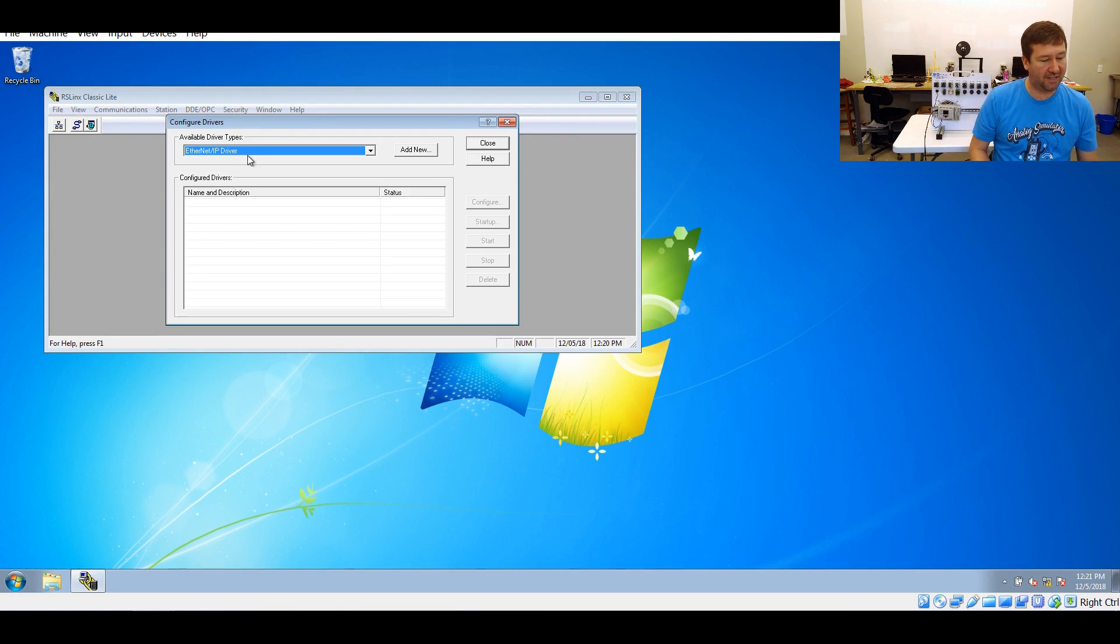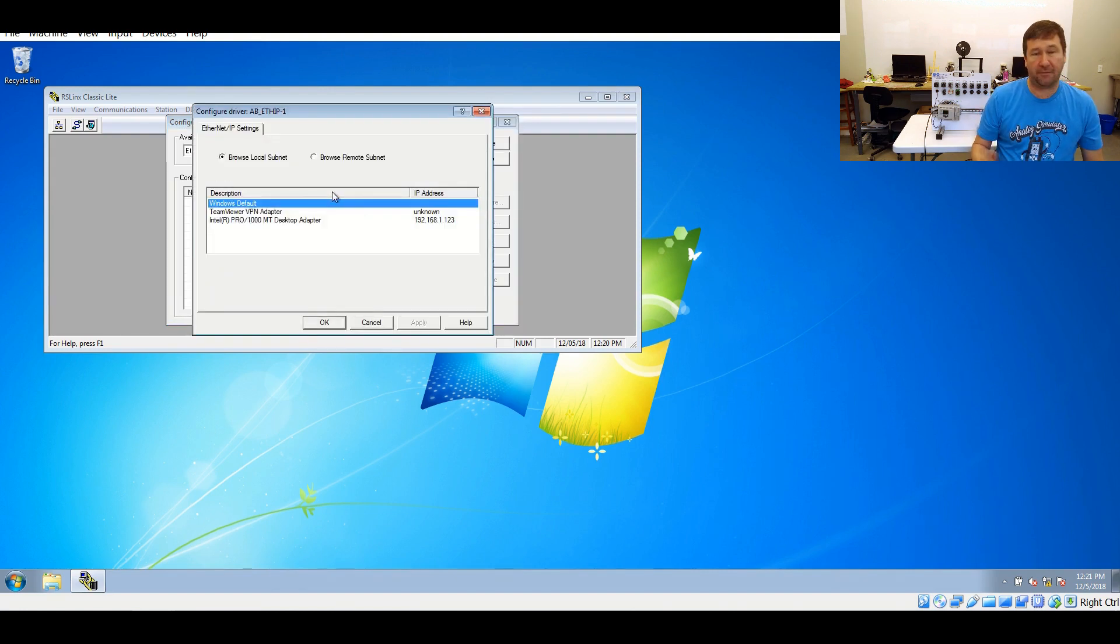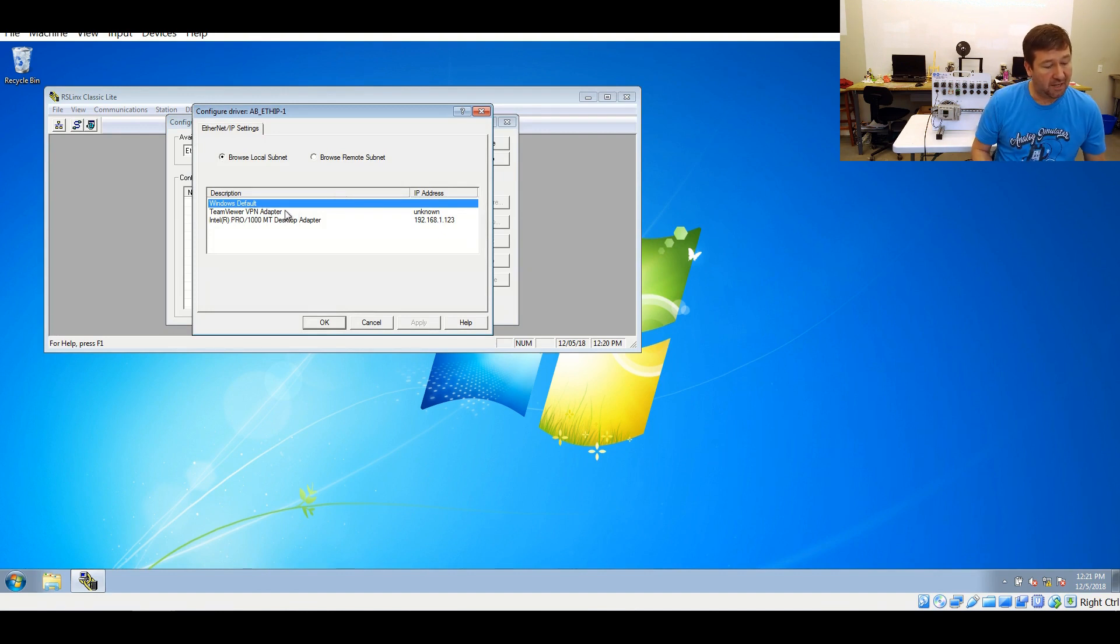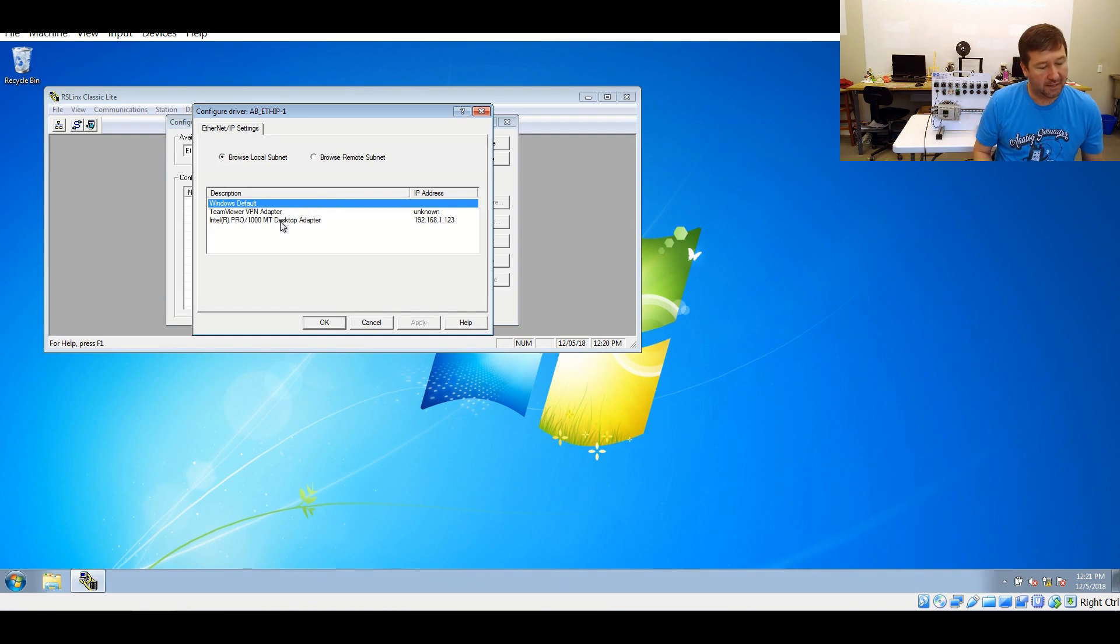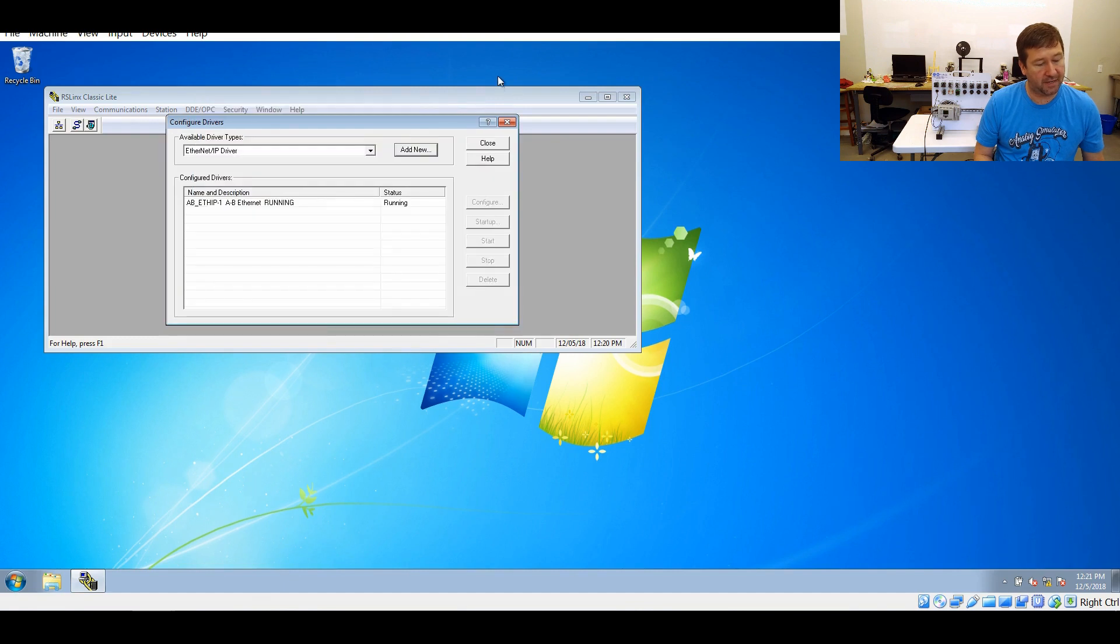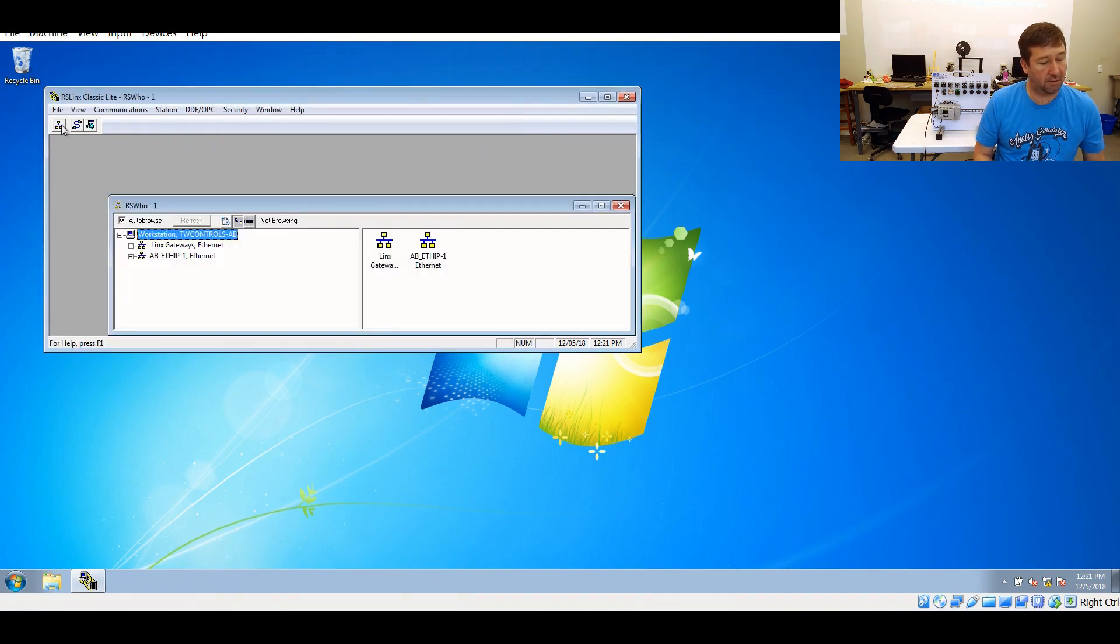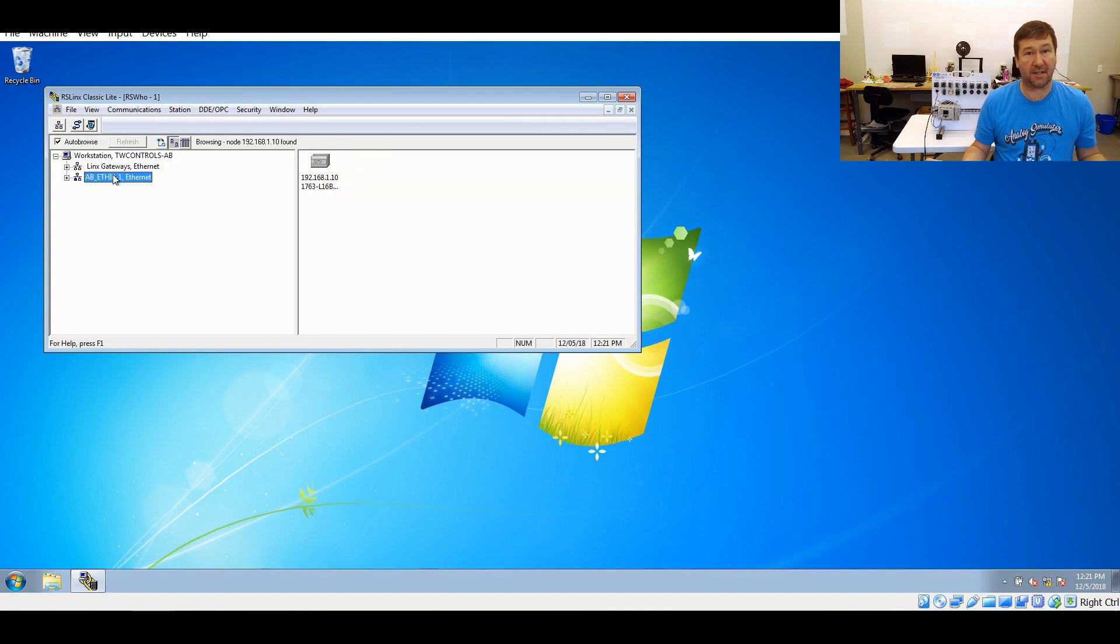To start with, we're going to select the Ethernet IP driver and click add new. Just leave this right at default. Now, if you have multiple adapters, you'll need to select which adapter it should be using. In my case, I have a VPN adapter for TeamViewer, but I'm going to use the physical Ethernet port. We close this and go to our RSWho. And you see right there is our PLC.